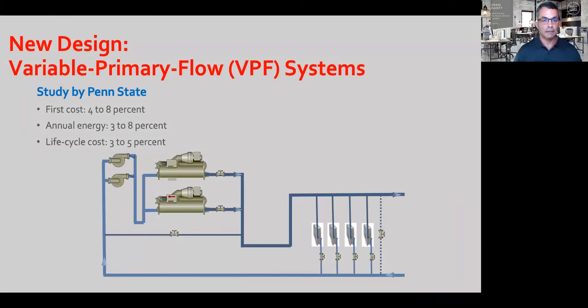One of the newer design systems is the variable primary flow system. The pumps are dedicated to the chillers, and the advantages are that you have only one set of pumps. The variable primary looks a lot simpler, and it saves on pumps and piping up front, so you could save about 4 to 8% on first cost. Likewise, you could save about 3 to 8% on your annual energy cost and about 3 to 5% on your life cycle cost. The variable primary flow system is designed to operate with variable flow through the chiller evaporators.